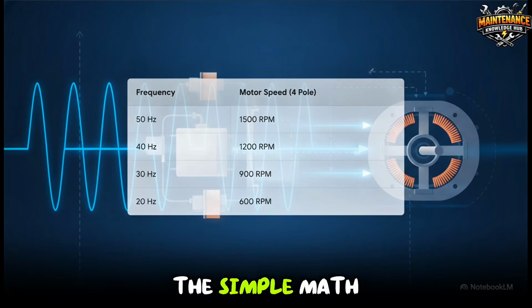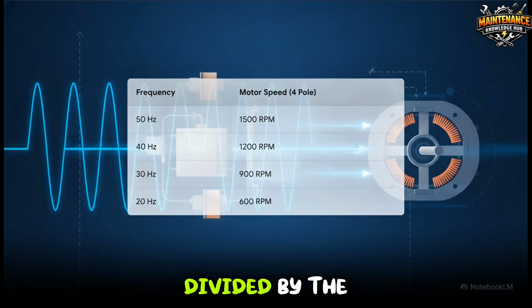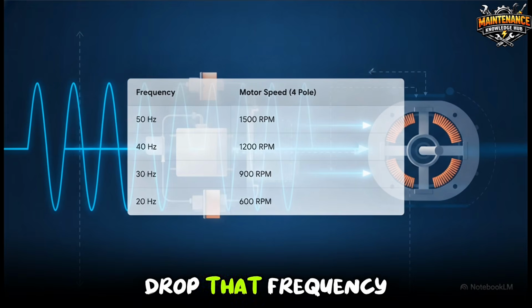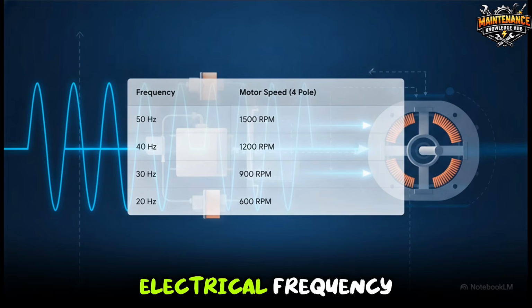Let's break down the simple math of how dropping that frequency directly controls the motor speed. The formula for motor speed in RPM is 120 times the frequency divided by the number of poles in the motor. So, for a standard 4-pole motor at 50 Hz, the motor runs at 1500 RPM. Drop that frequency to 40 Hz, it drops to 1200 RPM. Drop it to 20 Hz, you're looking at 600 RPM. You are literally just dialing the speed up and down by manipulating the electrical frequency.